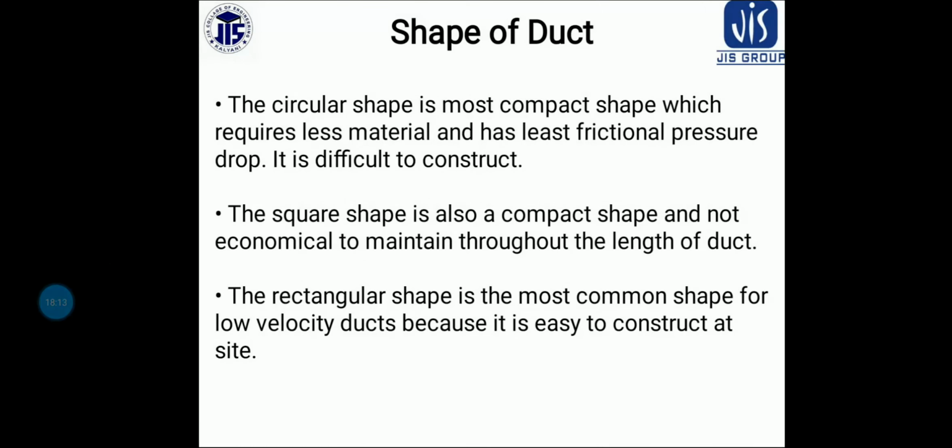So the successful operation of any air conditioning system depends upon the sufficient circulation of air in the air conditioned space. For selection of proper duct size, it is necessary to have a careful estimation of the pressure losses. Okay. Now the duct cost is about 20 to 30% of the total cost of the equipment required, and the power required by the fan contributes a substantial part of the running cost.